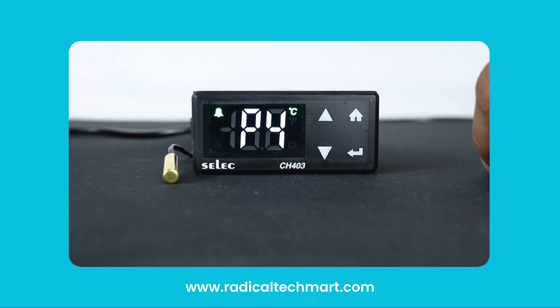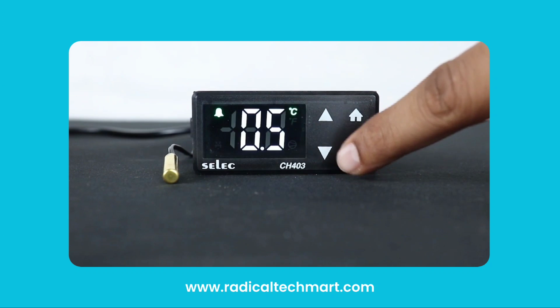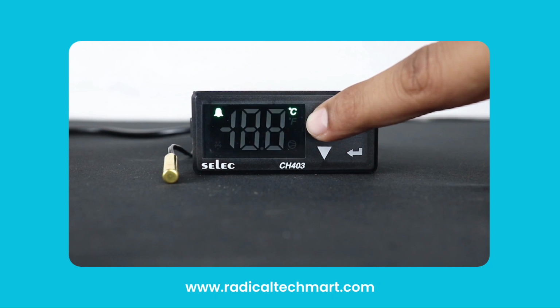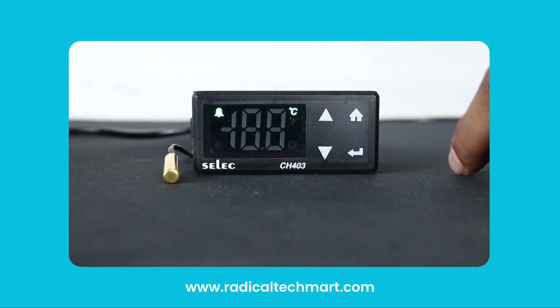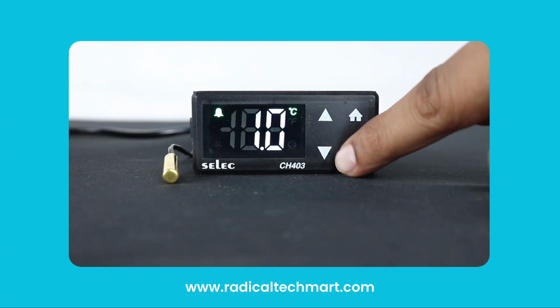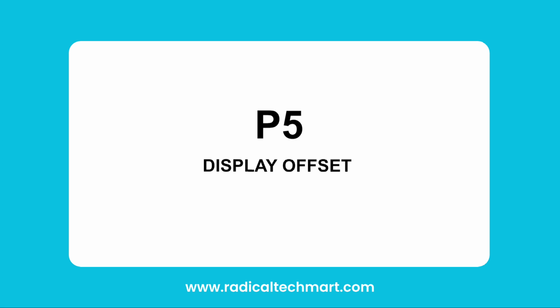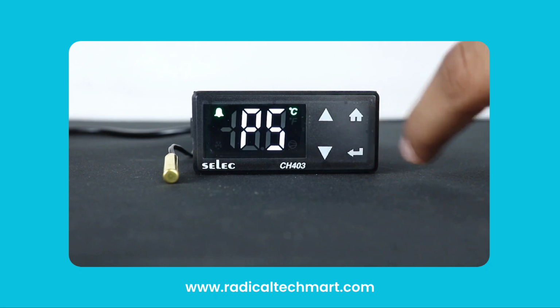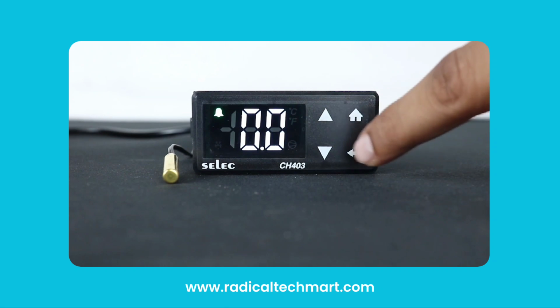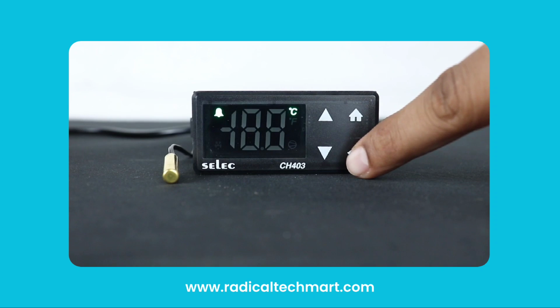This is used to prevent frequent on-off switching of the relay around the predefined setpoint. A hysteresis parameter is very useful to increase the compressor's life. The next parameter is P5, or display offset. It is used to calibrate the display readings according to another recorder or indicator.